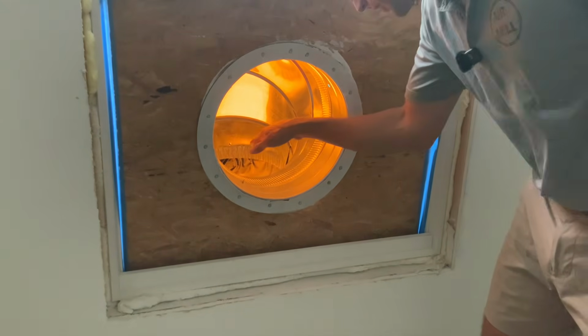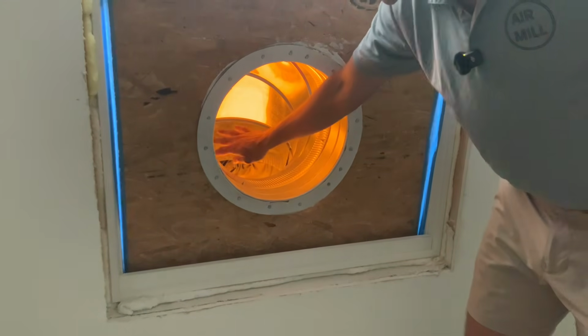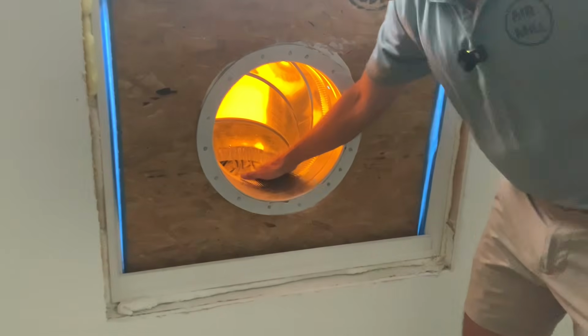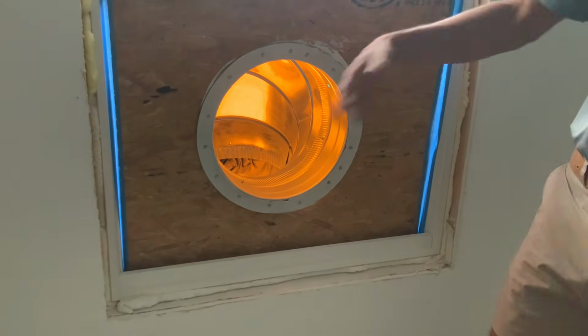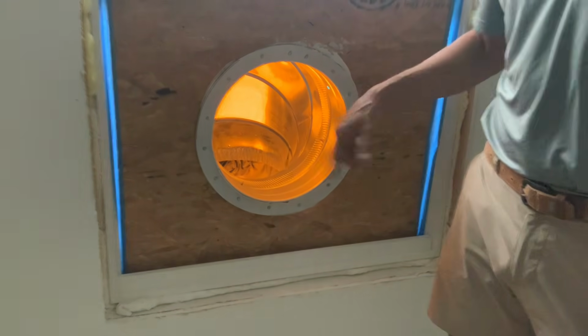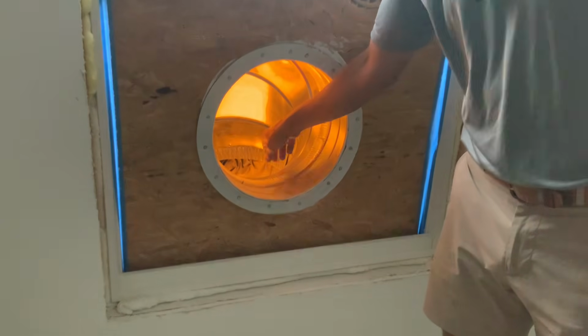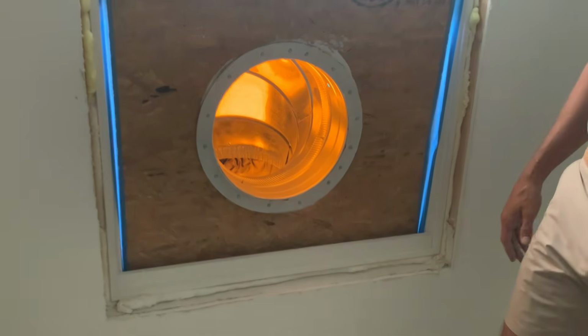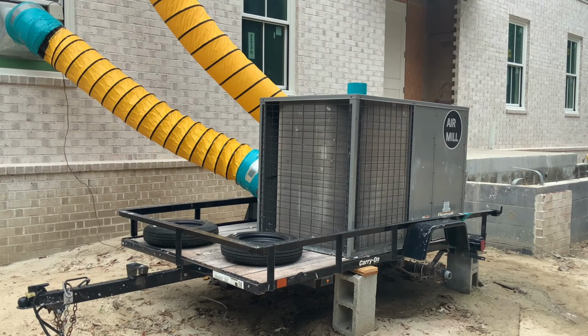And take a look at the ductwork attachment. Make sure that it's not ripping off or falling off anywhere. And when you pull the filters off down at the filter box, you can also check the ductwork connection. We can see in here, I stick my head in the duct, and there's like a little hole I wouldn't notice from the outside, so I'm gonna make sure to get some tape on that.